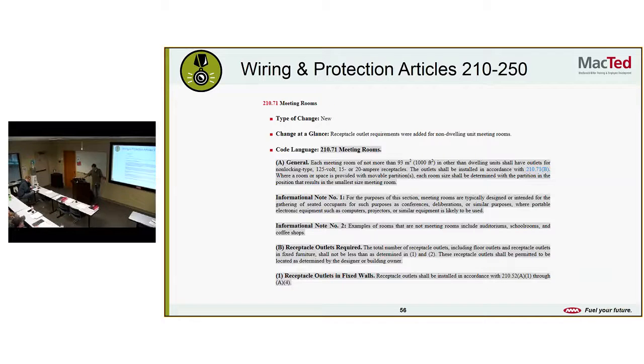All right, meeting rooms. Receptacle outlet requirements were added for non-dwelling unit meeting rooms. Looks like each meeting room of not more than 1,000 square feet in other than a dwelling unit shall have an outlet for non-locking type 125 volt, 15 and 20 amp receptacles. Outlets shall be installed in accordance with 210.71 where a room or space is provided with movable partitions. Each room shall be determined with the partition in the position that results in the smallest size meeting room.